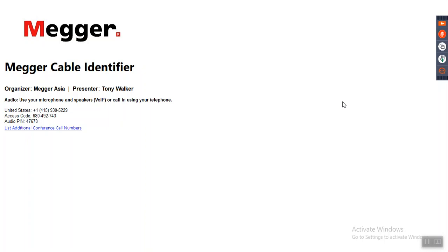You mean the CI can identify the cable is live or not live? It doesn't prove it's live or not live. What it proves is there's 50 hertz there. Don't take it as a proving dead unit. All right. Okay. There we go.